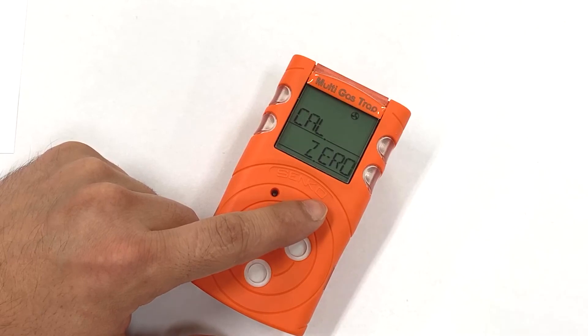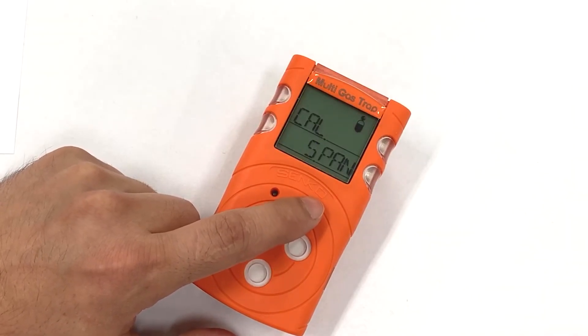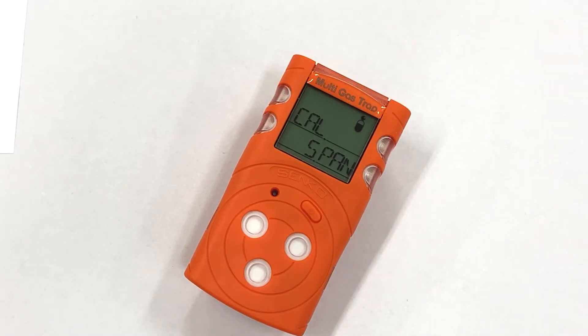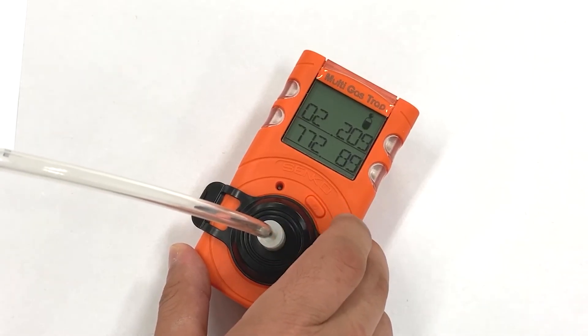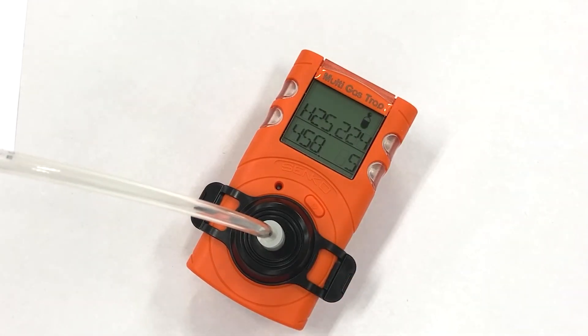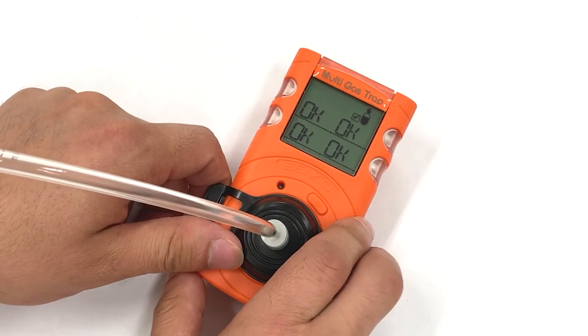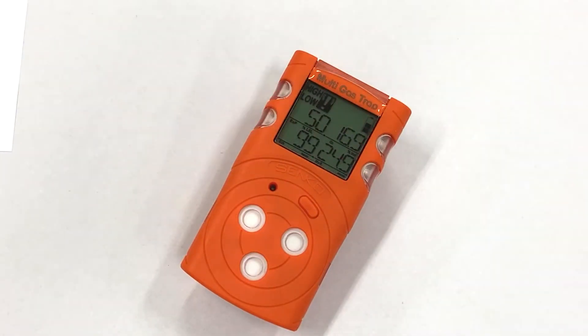Skip over to Cal Span, then apply the calibration cap, press and hold the button, and open the can of gas. It will take 90 seconds to perform a full span calibration on the sensors. The calibration has completed successfully and all sensors are okay and ready to work. Remove the calibration cap and the unit will return to normal operation.